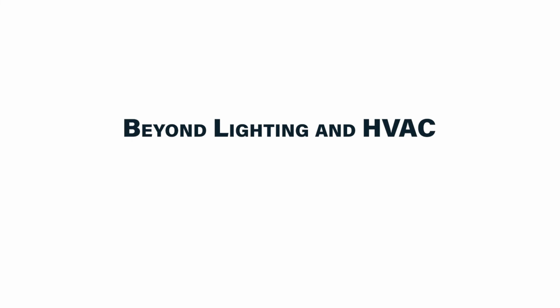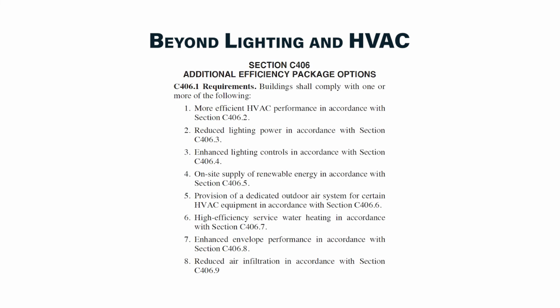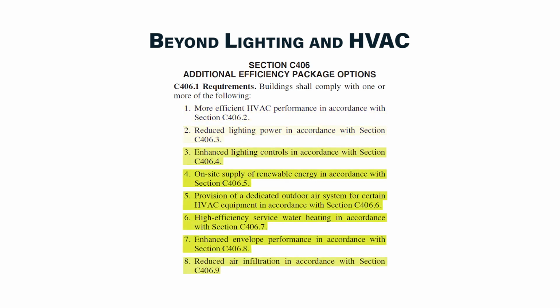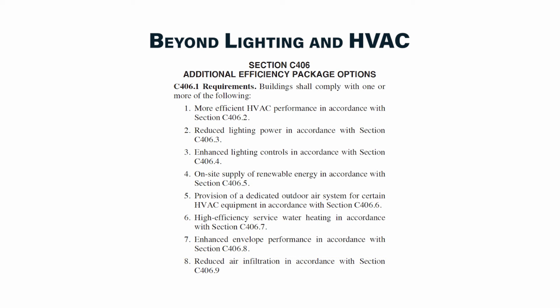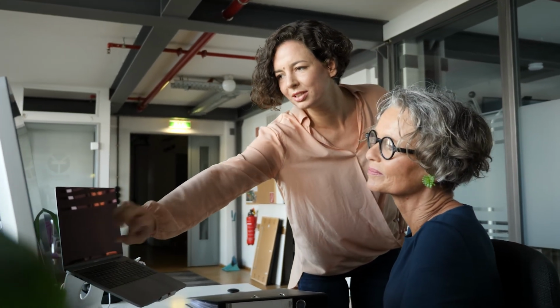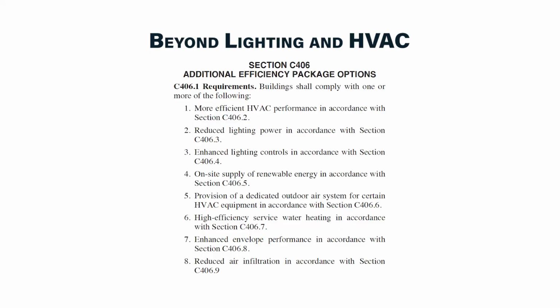Beyond the prescriptive requirements specific to lighting and HVAC controls, IECC Section C406 also requires compliance with one of 8 additional efficiency options. Most options require a system efficiency improvement beyond the basic prescriptive requirement. Design teams do have the flexibility to select the option that best fits their project. 2 options that I see most frequently selected, perhaps because of their simplicity, are either option 1 or option 2. Option 1 requires HVAC equipment efficiency to be 10% better than the prescriptive values for the type and size of each unit. Option 2 reduces the whole building lighting power density by an additional 10%.